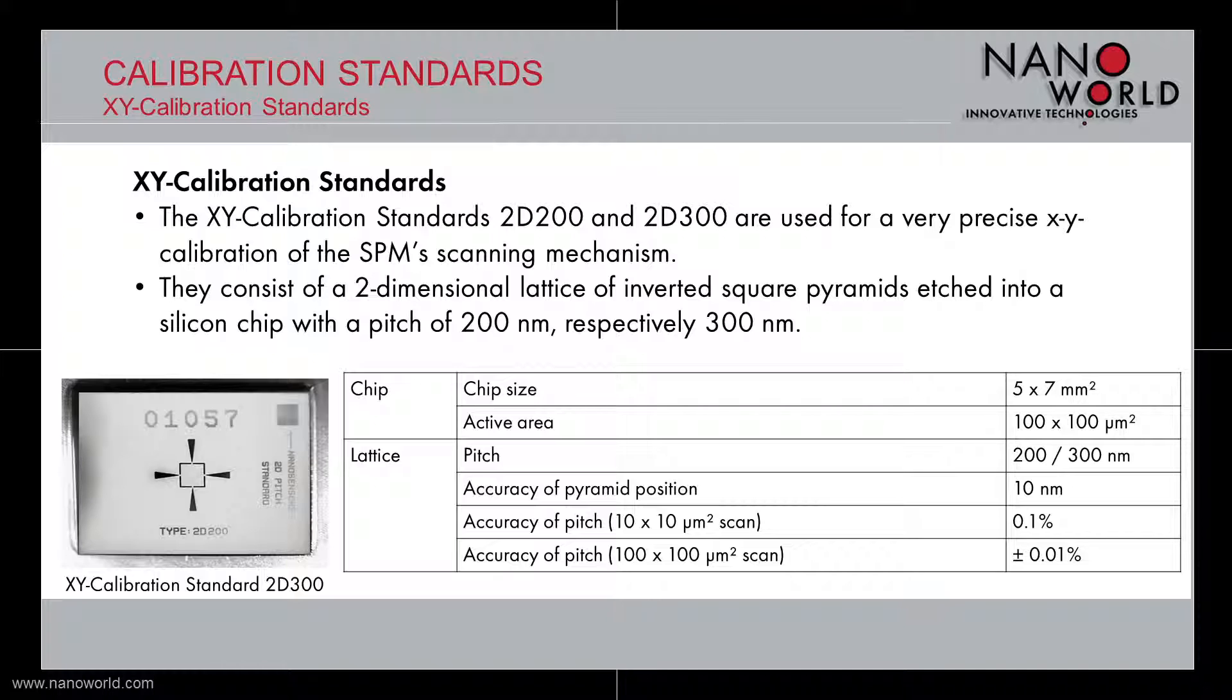They consist of a two-dimensional lattice of inverted square pyramids etched into a silicon chip with a pitch of 200, respectively 300 nm. The accuracy of the pitch is 0.1% on a 10x10 μm² scan area and drops down to 0.01% when the full active area of 100x100 μm² is scanned.